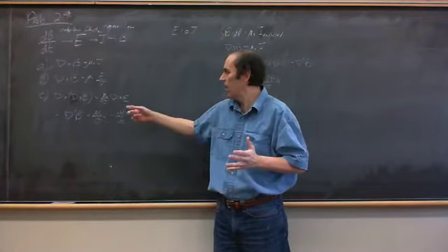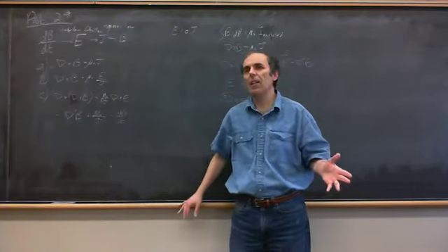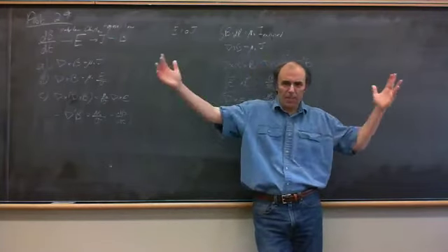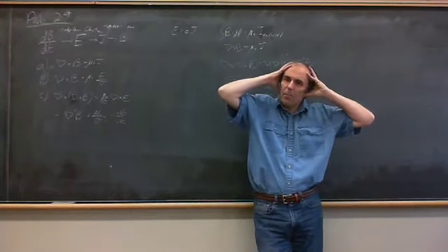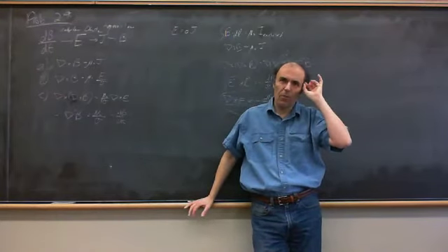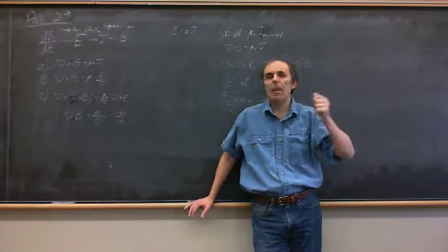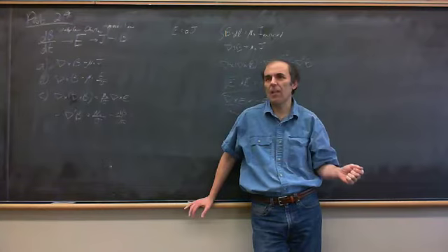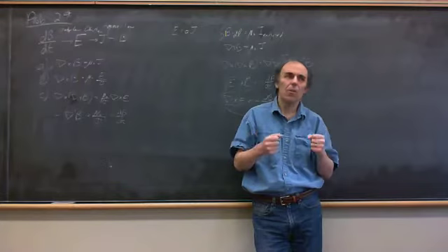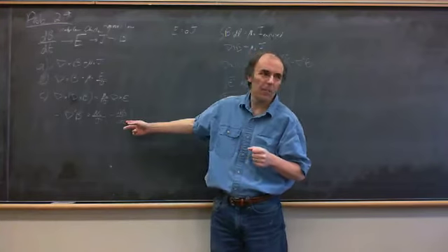So if you put in the frequency and the rate of change that corresponds to the radio frequency magnetic field, you can calculate the skin depth. It turns out the skin depth is still pretty big. If the skin depth is a meter and your head's a couple tenths of a meter, the skin depth's not important. It's only when skin depth happens over a very narrow, small length that it's important. So in magnetic resonance imaging, skin depth's not really that big of a deal unless you use stronger and stronger static magnetic fields, which drives the radio frequency up higher and higher. You can actually get where there's a little bit of effect from skin depth.